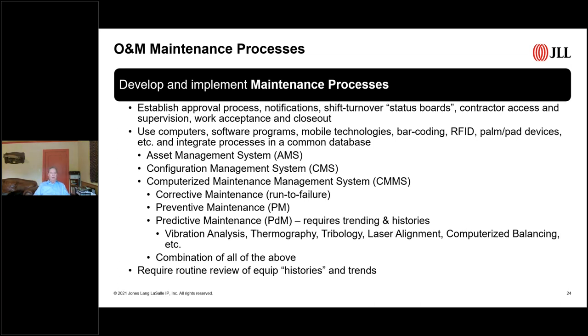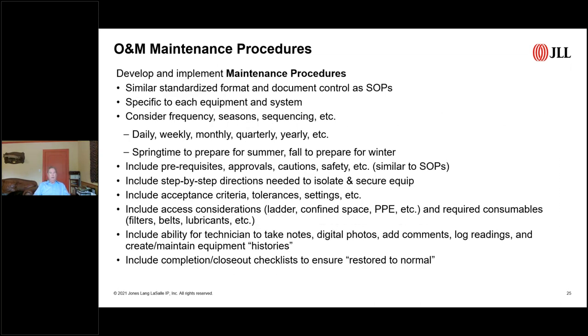Another important thing to include in your maintenance process is the ability to capture data for history, and to review, assess, and analyze that data over time. It's not good enough to just keep collecting data and archiving it, making sure things are within specifications. It's more important, or as important, to trend that data over time and see how things are starting to degrade, or to see that among five identical pieces of equipment, one keeps failing more often than the others. These histories help you make sure you're approaching maintenance the best you can.